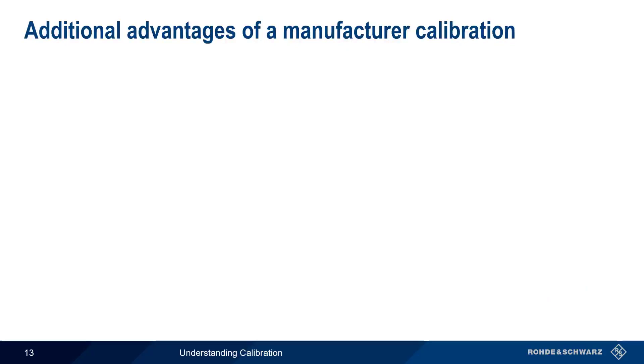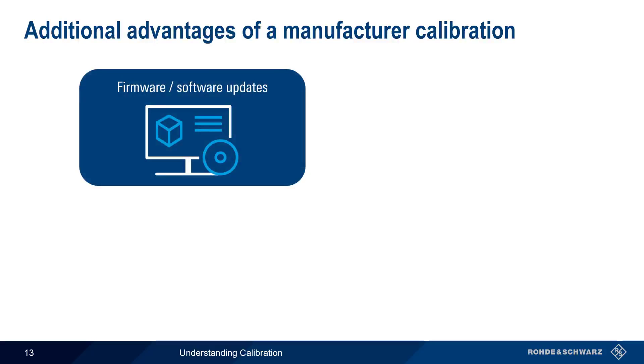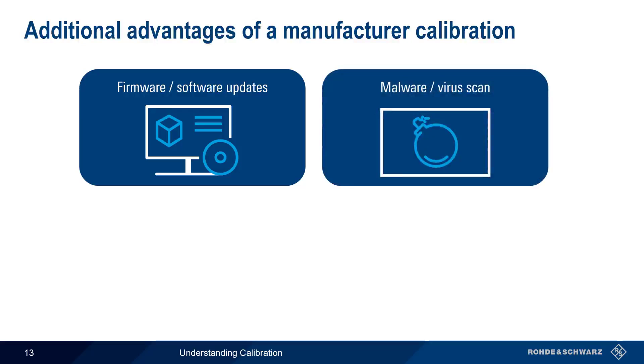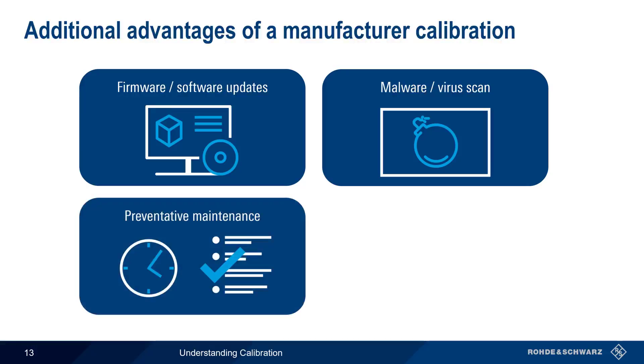There are some additional advantages of manufacturer calibration over third-party calibration. Updating the instrument's firmware, software, or operating system is a standard procedure during a manufacturer calibration. In addition, instruments are also scanned for viruses and other types of malware in order to ensure the safety and performance of the instrument. The manufacturer can also perform various types of preventative maintenance or hardware updates as part of the calibration — third parties normally would not have the knowledge or expertise to perform these changes, which are often provided free of charge.